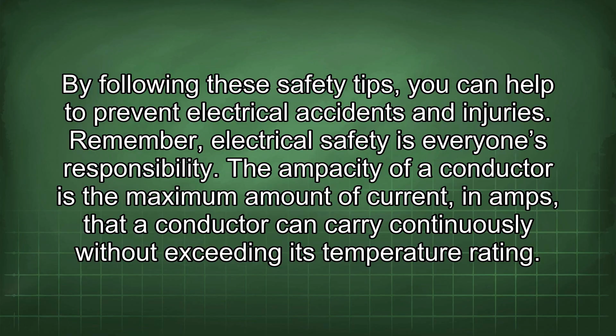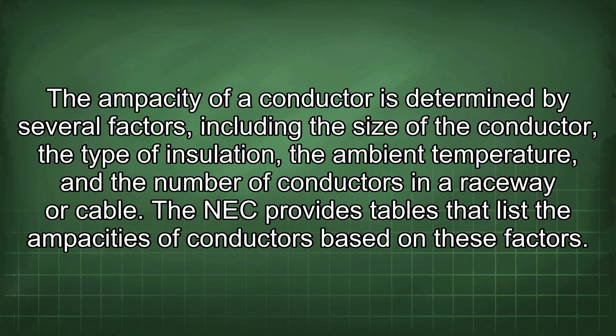The ampacity of a conductor is determined by several factors, including the size of the conductor, the type of insulation, the ambient temperature, and the number of conductors in a raceway or cable. The NEC provides tables that list the ampacities of conductors based on these factors. It is important to select conductors with the appropriate ampacity for the application to prevent overheating and potential fire hazards.